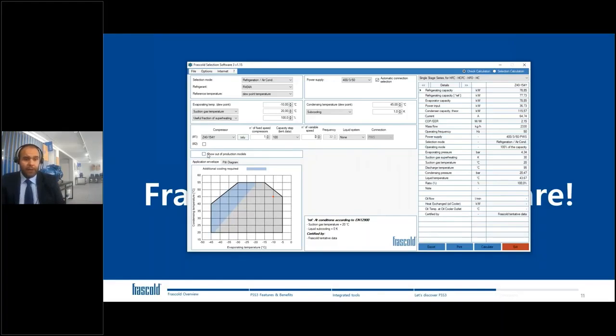Here you have the possibility to show out of production models. Maybe you have an old compressor that is still running, so you maybe want to change the refrigerant. Clicking here, the list of compressors changes, and in brackets you have the old model. In the bottom part, we have the application envelope for each compressor. So you have expressed, in terms of evaporating temperature and condensing temperature, the limit in which you can operate with this compressor.